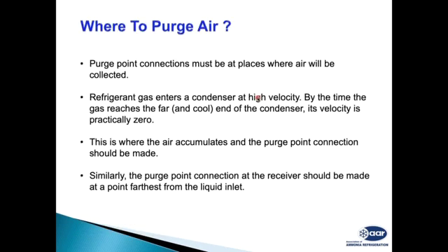As I said, for purging of the air, proper location of the purge points is very important. For example, when doing manual purging, when you are shutting down the condenser, you have to purge from the topmost point of the condenser or at the inlet point of the condenser. That is the topmost point of the system. But with automatic purging, this totally changes. In automatic purging, we need to separate the air and the gas. In our refrigerant system, the gas coming from the compressor to the condenser may contain air.